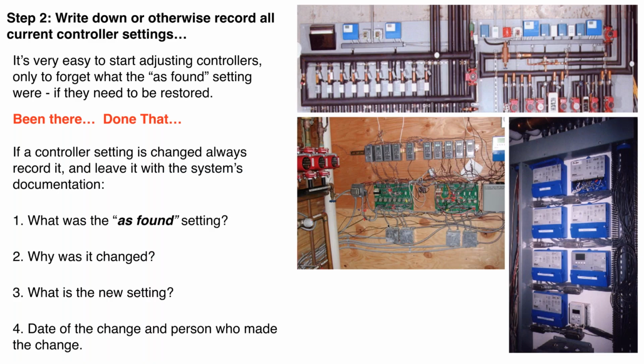So if a controller setting is going to be changed, make sure you record it. What was the as found condition? Why was it changed? What was the new setting? And what is the date and the person who made that change? That's going to help you. It could help a future technician that is trying to troubleshoot the system as well. So documentation of what you're doing, especially when it comes to controls, is really important.